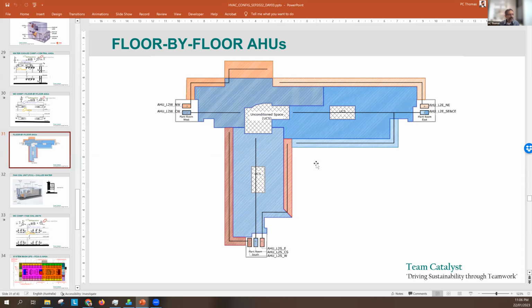Now, the reason the engineer has broken it down in this case is because it's what we call a floor-by-floor system. So on each floor there are air handling units treating these different zones. You can see here there's an air handling unit handling this perimeter zone, another one handling those two zones we are calling north perimeter zones. There's a north arrow missing here. And these ones are more internal zones.